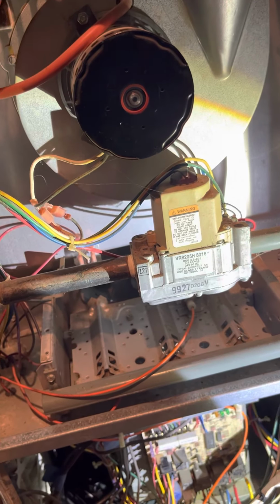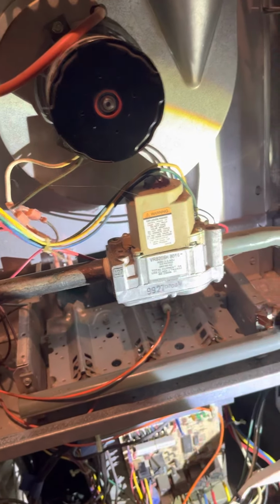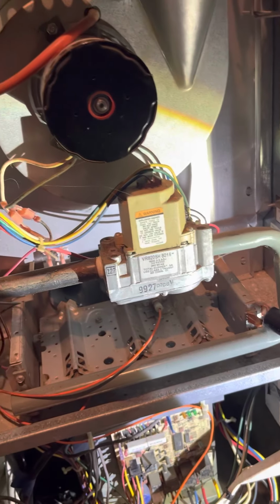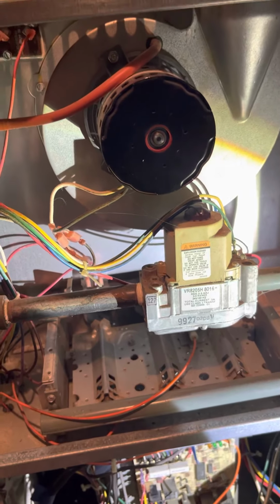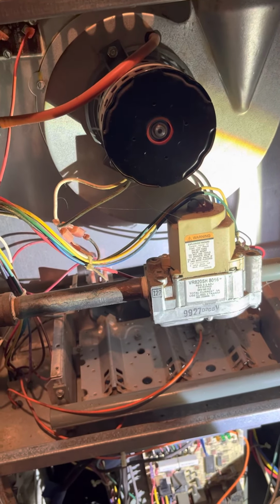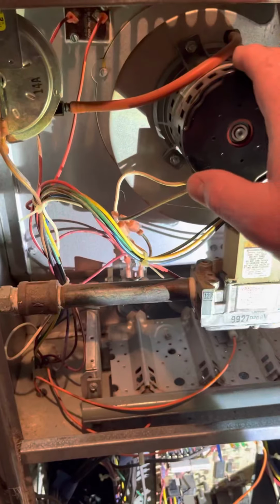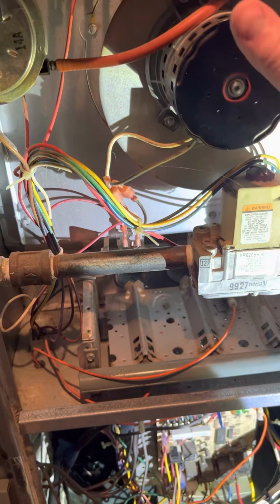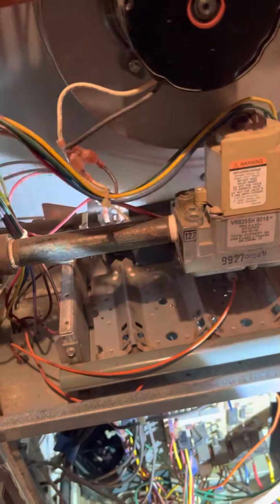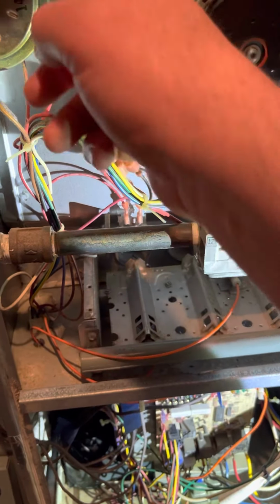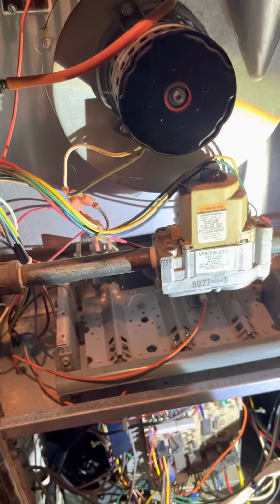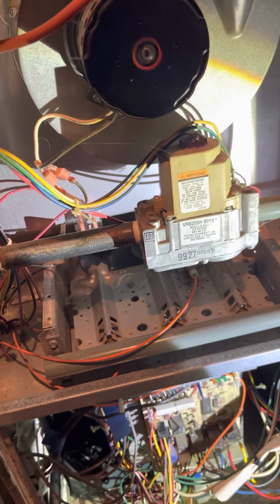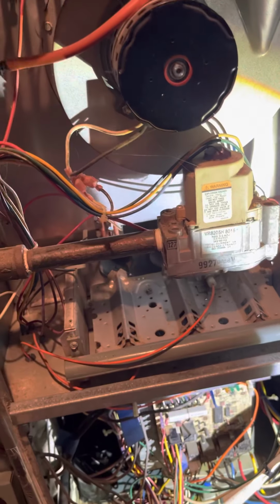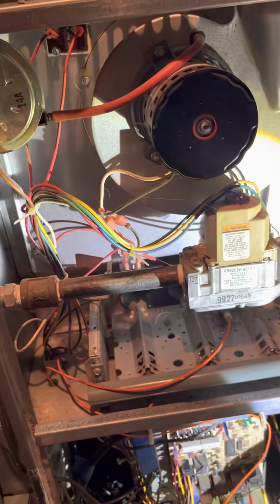I hope that's helpful. That gives you an overall picture of the operation of the furnace very quickly, and it helps you to pinpoint what point in the sequence of operation you have a problem. So if you have inducer and nothing on the pressure switch, then either the inducer fan inside here, the impeller, is not pulling negative, or you have a crack in your hose, you have a bad pressure switch. But your test light helps you to get to the heart of the problem a lot faster than pulling out your meter. At least I've found that to be true.